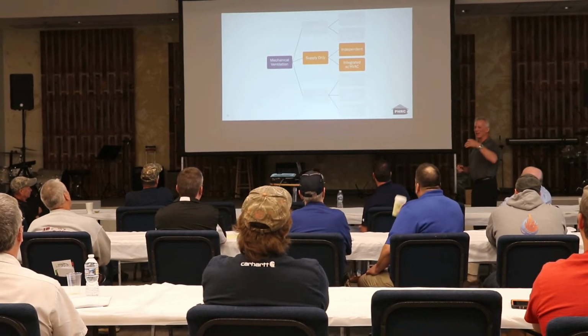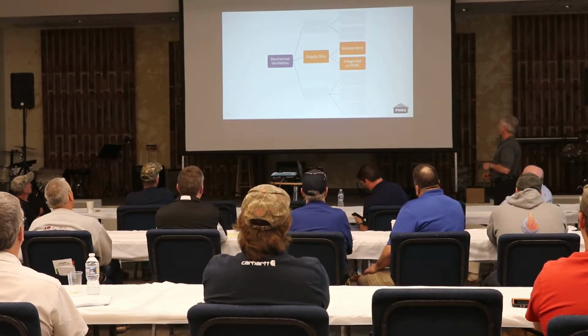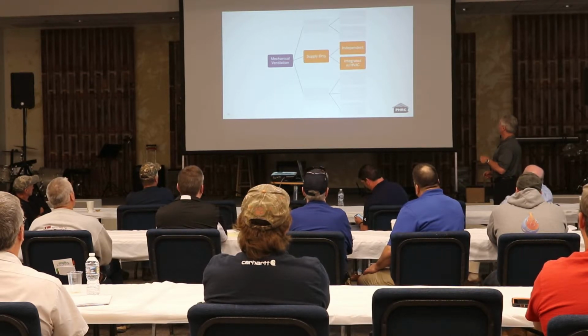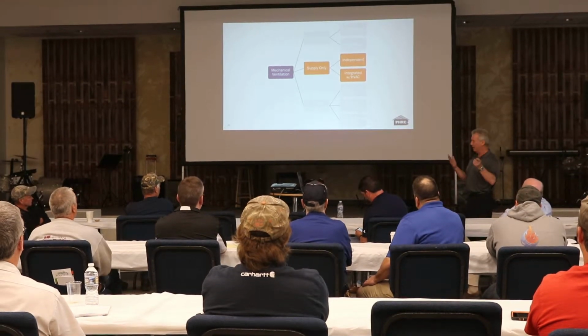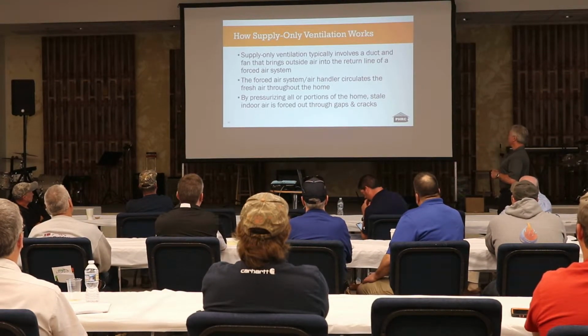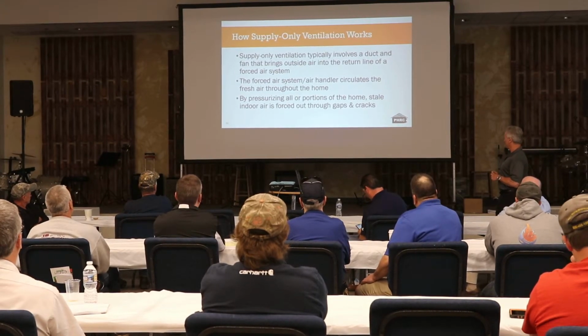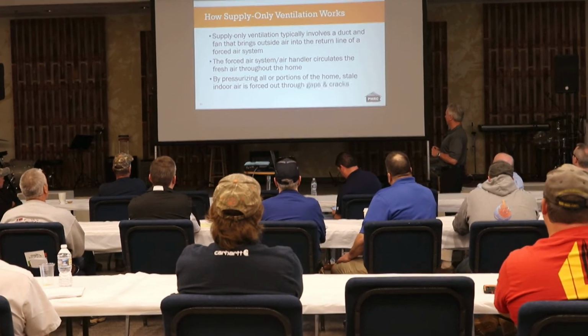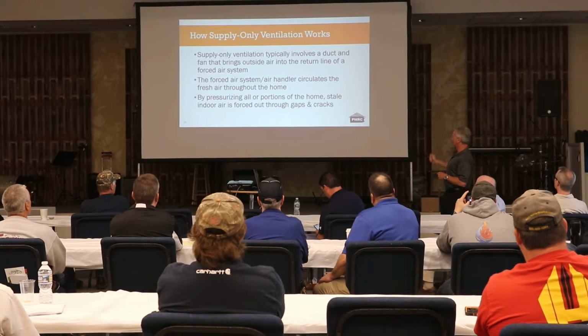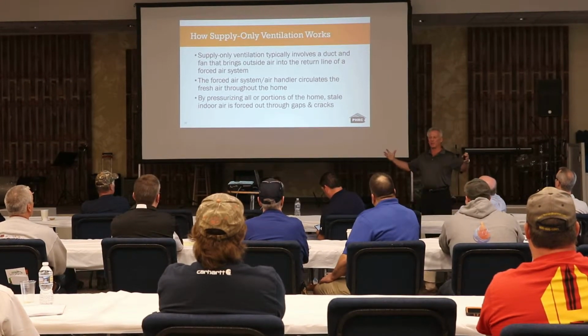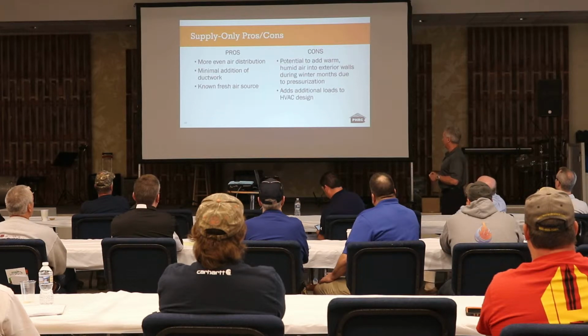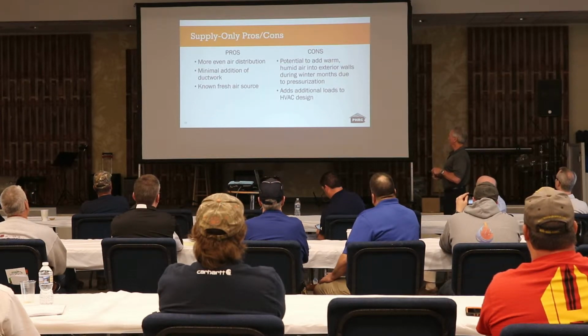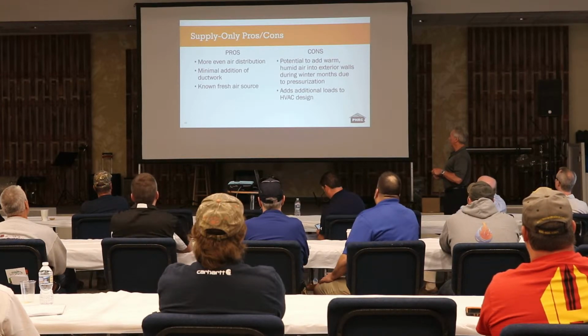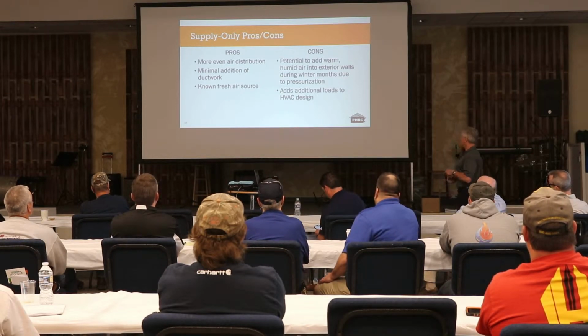Okay, so by asking the question, obviously we got ahead of the slides a little bit, but supply-only methods are independent, or you can integrate them with the HVAC, and I think we would agree that makes the most sense. It typically involves a duct fan that brings air into the return line of a forced air system, which circulates the air for the home. Now, according to this slide, we're pressurizing all portions of the home and forcing air out, so we have a positive pressure in that house. Pros: more even distribution, minimal addition of ductwork, and you have a known source of where the outside air is coming from.